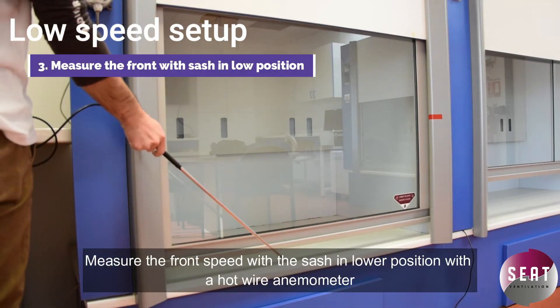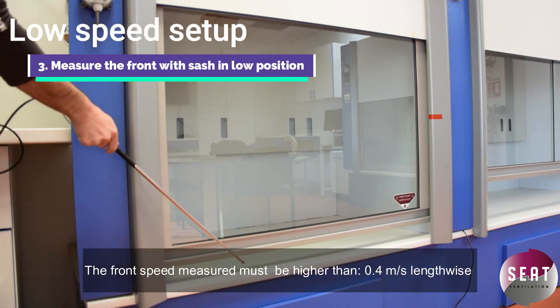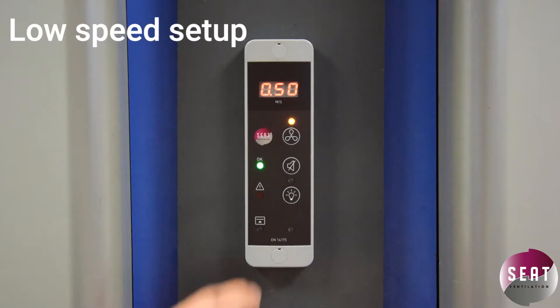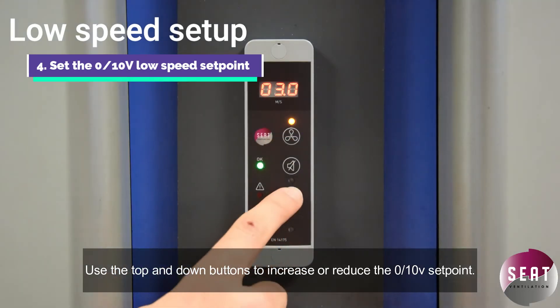Measure the front speed with the sash in the lower position using a hotwire anemometer. The front speed measured must be higher than 0.4 meters per second lengthwise. Use the top and down buttons to increase or reduce the 0 to 10 volt setpoint.